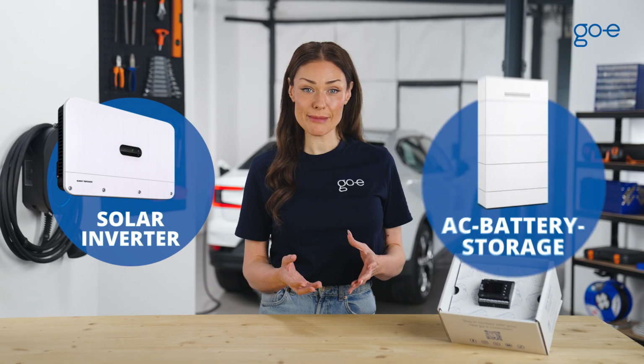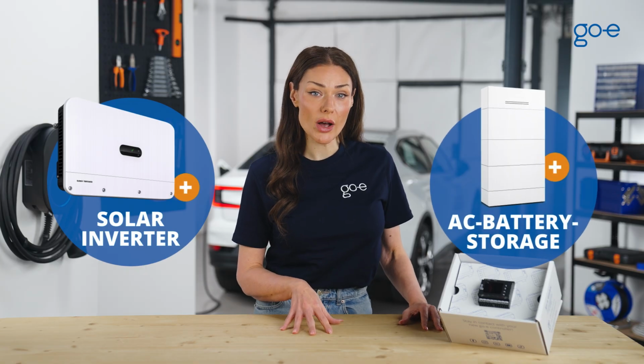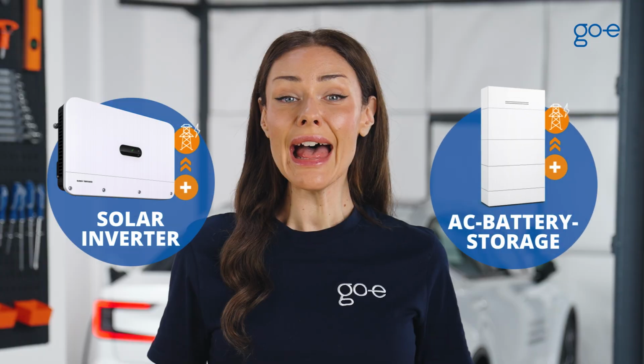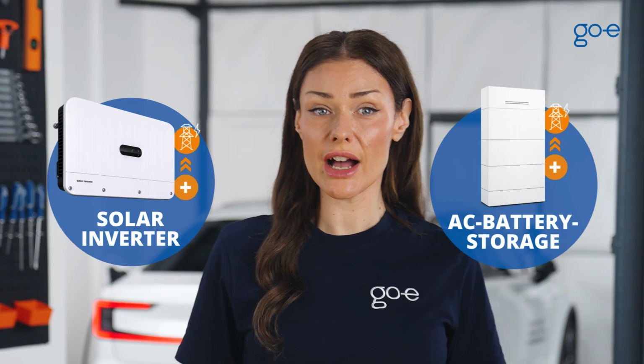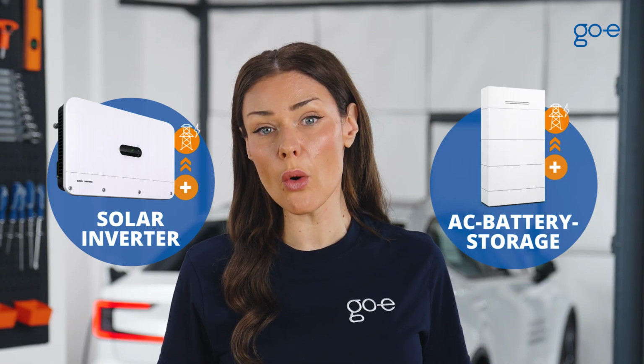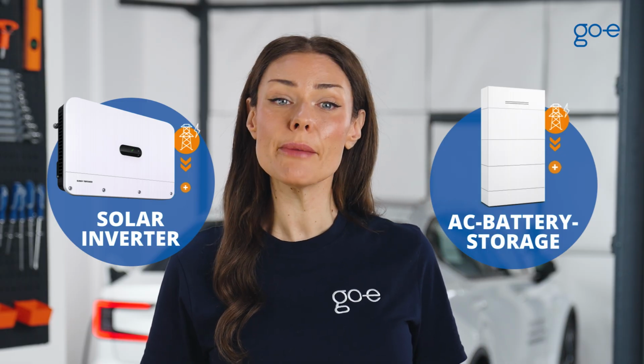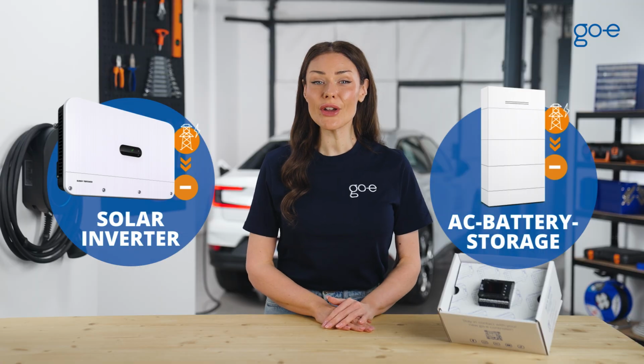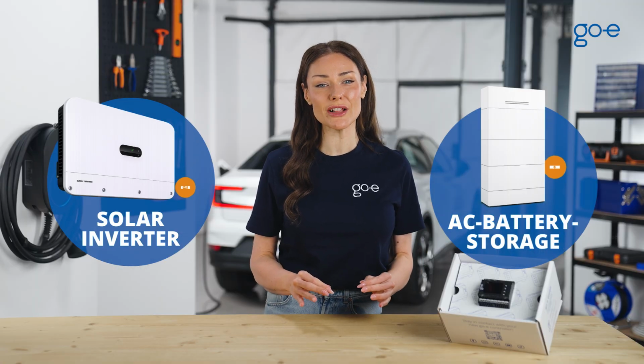In general, power should show as positive when you're importing energy from the grid. For a solar inverter or an AC battery, the power should be positive when exporting to the grid. However, when the battery is charging or the inverter consumes more in standby than it generates, the power can be negative. When no current is flowing, the power value should be close to 0. It's very important that the correct phase is set as the voltage reference.